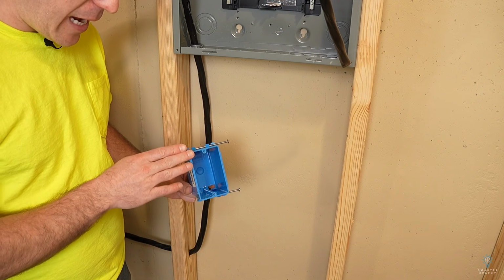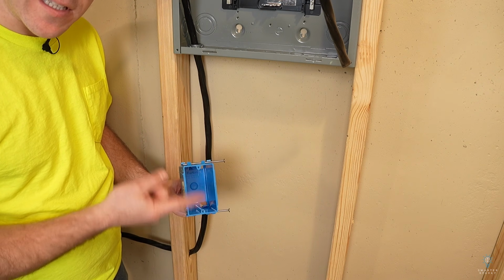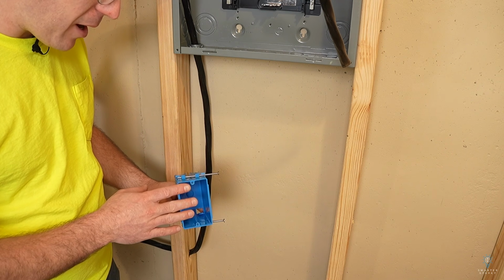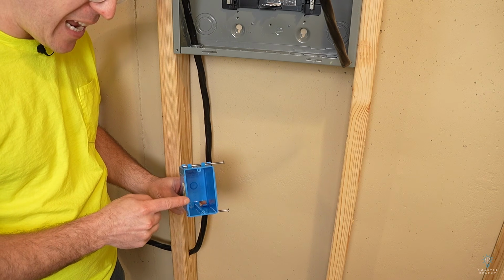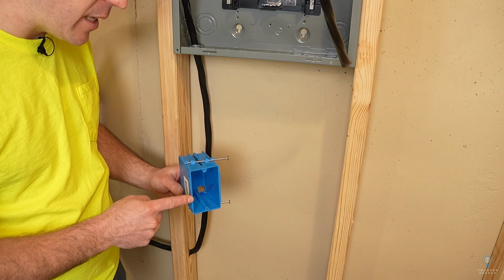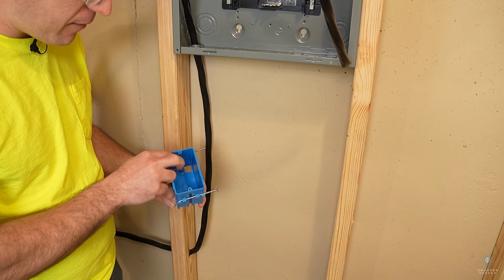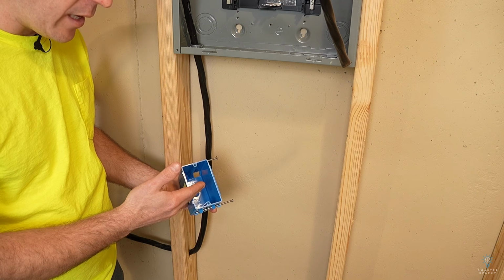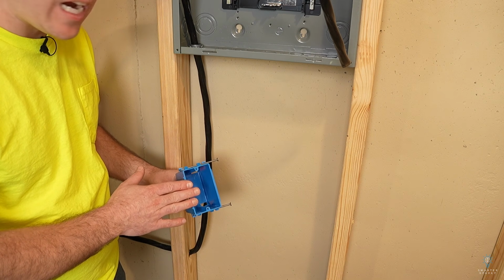Back in the video I did on installing a receptacle, if you haven't seen that, make sure you go check that out. We talked about how we actually need to staple within 8 inches of these boxes. And the reason for that is these boxes don't have an internal clamp. So when there is no internal clamp, we have to staple within 8 inches.